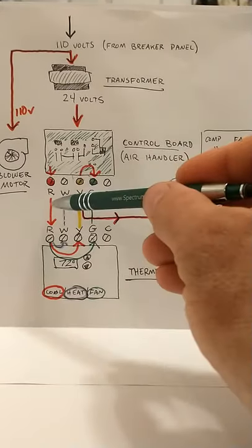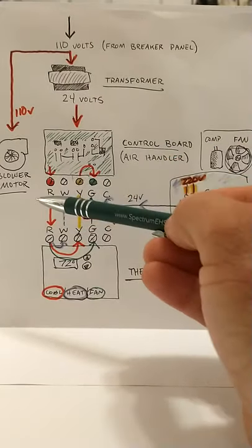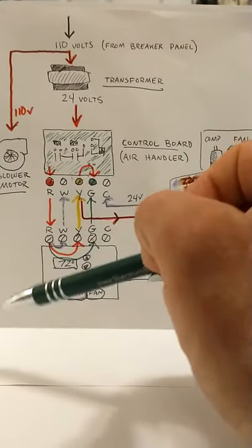You can also wire it to your 24 volt wire. So, for example, you would take your two wires from your float switch. One end would go to the R at your air handler. The other end would go to a red wire up to your thermostat. And if that float switch lifted...